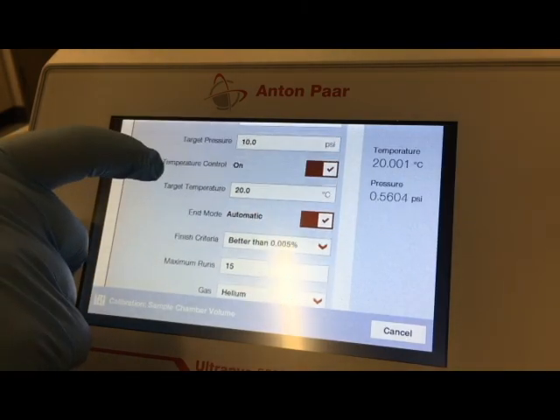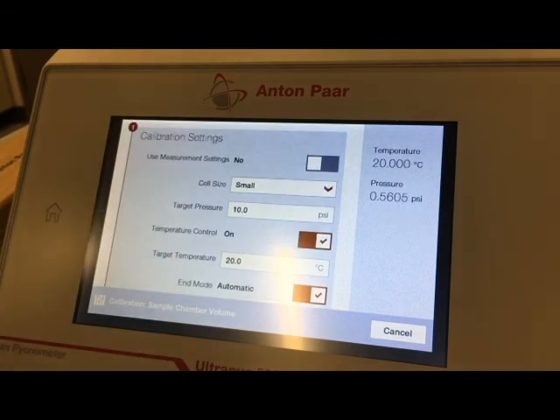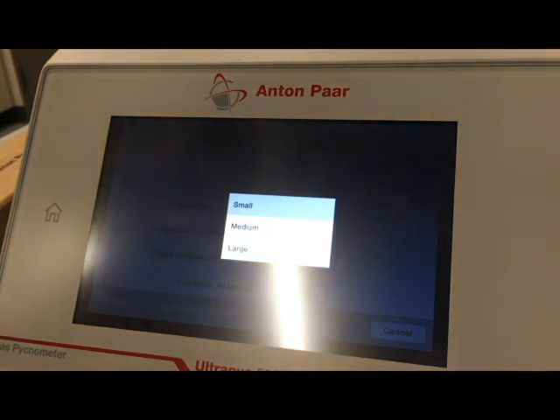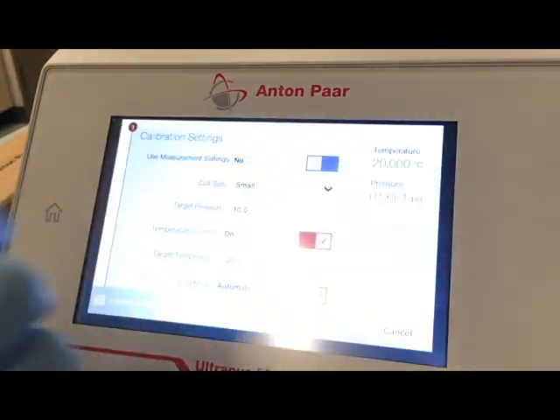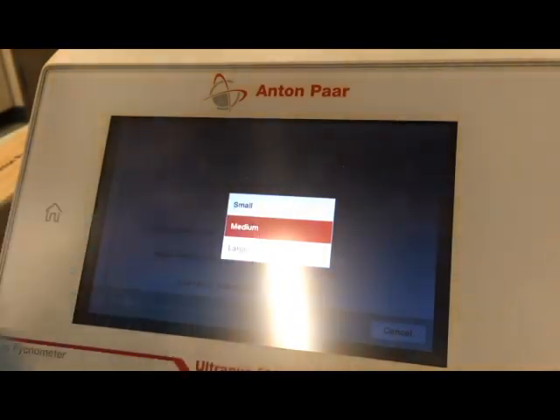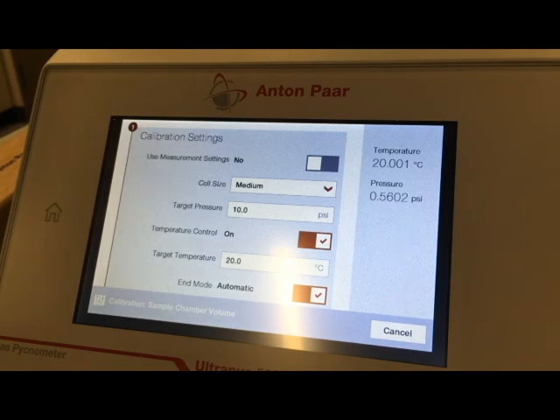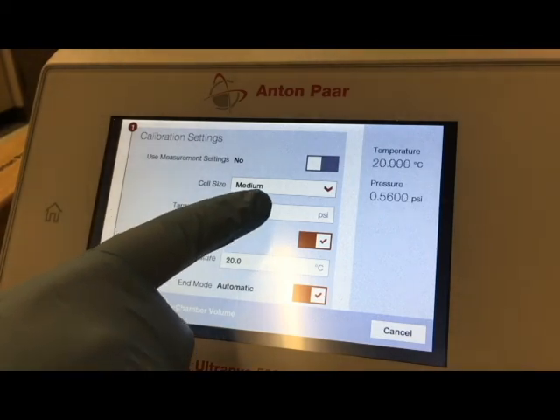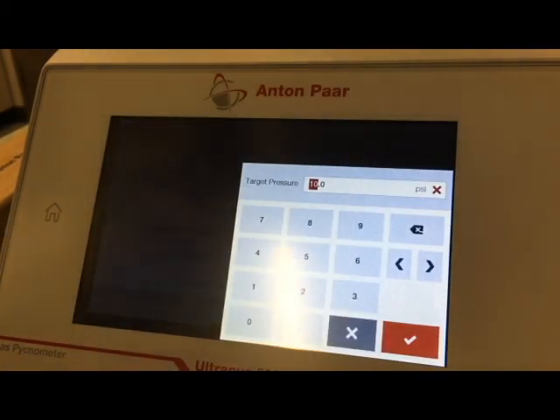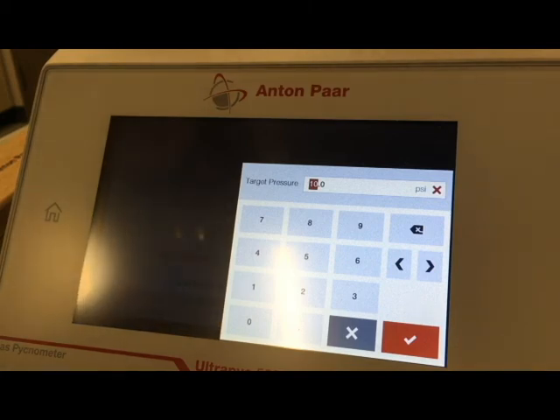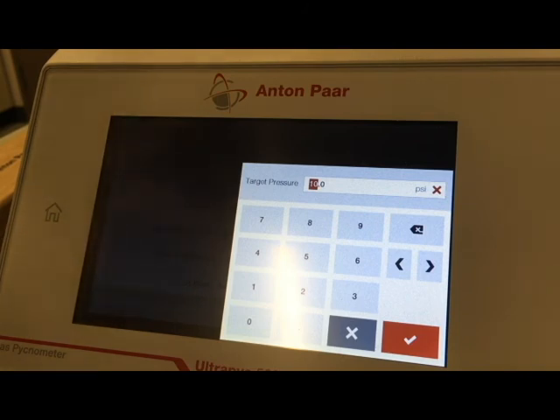You want to set up the settings to be as similar to your run settings as possible. Cell size, we can select from small, medium, or large. If you are using the micro, meso, or nano cells, please select small. Otherwise, select the corresponding cell. We are using medium today. Set your target pressure. That can be anywhere between 2 and 20 psi. Whatever you set your target pressure to be, you want to set the regulator at the tank of helium to be about 2 psi above the target pressure.